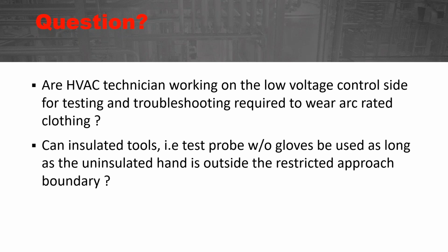If it is just low voltage, and if there's no other dangers, then, and we'll talk about this later, there's another question or two coming up about this. So then you would not be required to wear arc-rated clothing. 70E says when an employee is working within the arc flash boundary, he or she has to wear protective clothing and other PPE in accordance with 130.5.